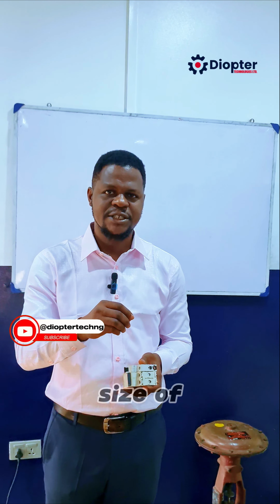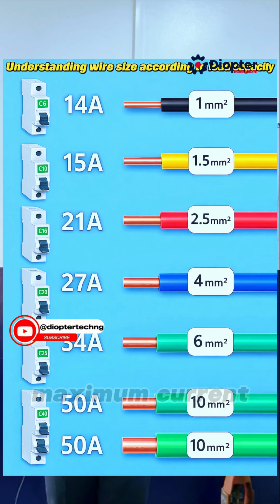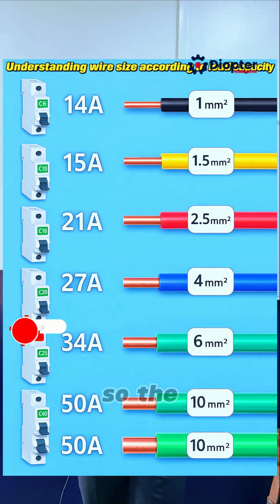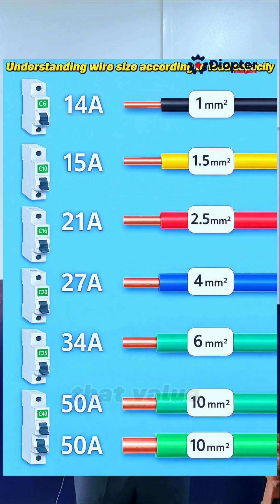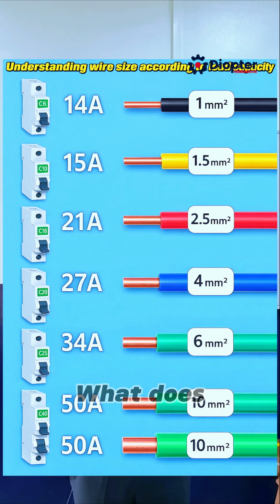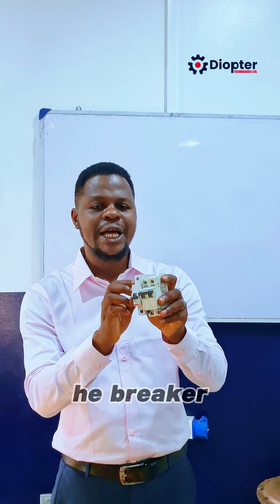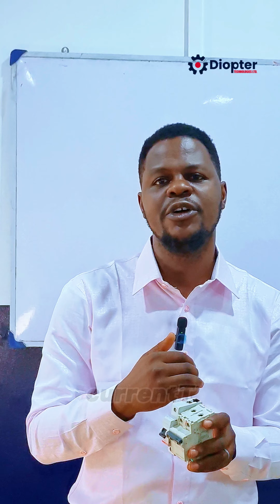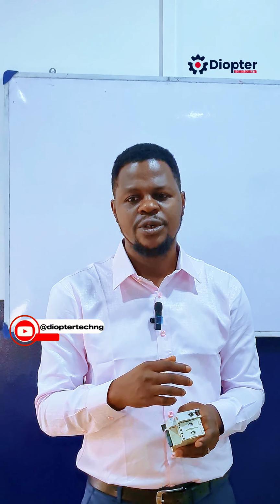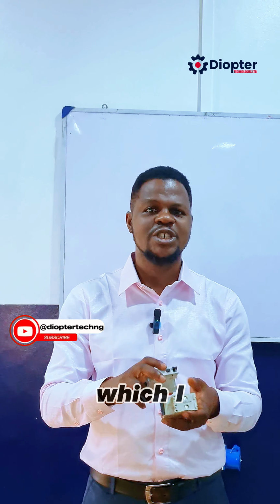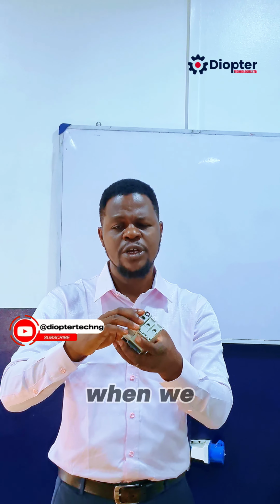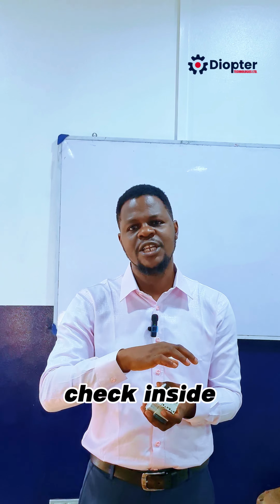Each size of cable is rated for a certain maximum current, so the breaker must not exceed that value. So what does the breaker do? The breaker detects excessive current and automatically trips to protect the cable. It does that using internal parts, which I will explain when we check inside the circuit breaker.